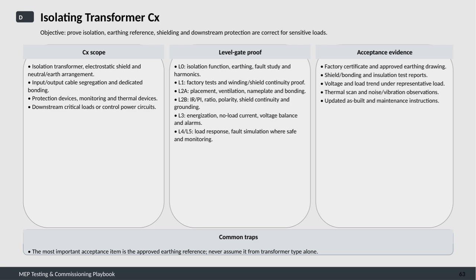We look at the isolation transformer itself, including the electrostatic shield and how the neutral and earth are arranged. It's also important to confirm proper segregation of input and output cables, as well as dedicated bonding connections. Protection devices, monitoring systems, and thermal devices downstream are evaluated too, along with critical loads or control power circuits they serve. The process is structured into level gates, which help us systematically validate each step.